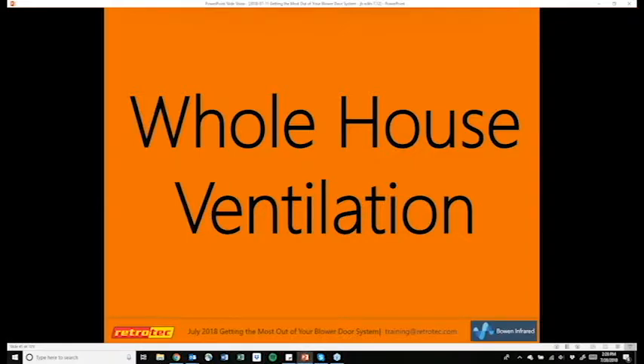So that was apps, and so now we'll talk a little bit about whole house ventilation. And I know this is kind of a random topic to throw in, but you can actually use your blower door to verify if certain types of whole house ventilation are working properly. And the type that I'm referring to is positively pressurized ventilation. And so that's going to be like your ASHRAE 62.2, where you have an AirCycler fan and a motorized damper that ties into your return system.